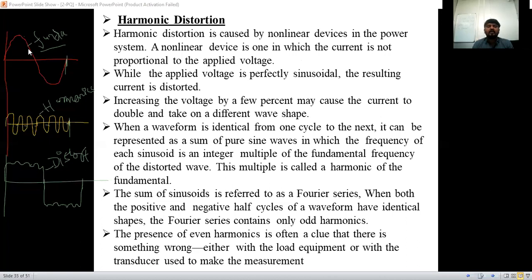So the non-linear devices, the switching devices or electronic devices, whatever it is, such as cycloconverters, inverters, rectifiers, these circuits produce the non-linear harmonics. Because of these harmonics, the current value increases, so current distortion will occur. Because of the high current or harmonics, voltage will be dropped, so voltage distortion will occur.